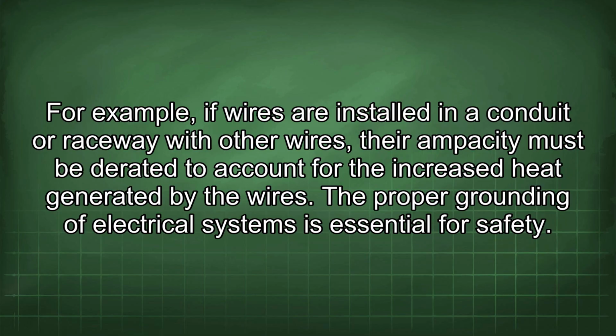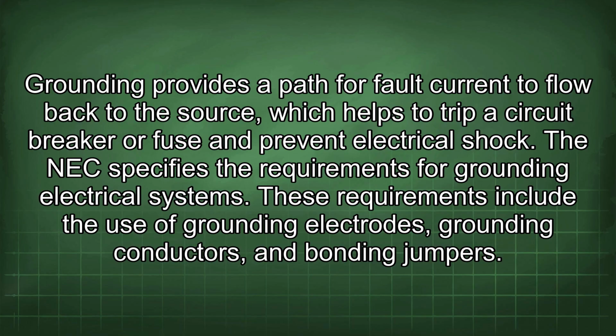Proper grounding of electrical systems is essential for safety. Grounding provides a path for fault current to flow back to the source, which helps to trip a circuit breaker or fuse and prevent electrical shock. The NEC specifies the requirements for grounding electrical systems. These requirements include the use of grounding electrodes, grounding conductors, and bonding jumpers.